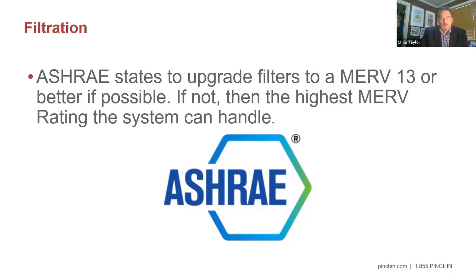The downside, of course, is that the minute you increase your filtration, your airflow may now decrease. If you haven't got the fan power to pump air through that filter, we may be reducing the amount of fresh air in our system. So it's basically a case of not wanting to reduce that fresh air. I want a filter, and the better the filter I can use, the better. But more fresh air is as much a value to us as anything.